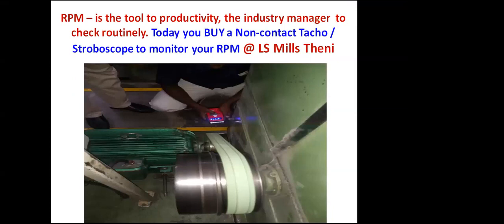RPM, as I was telling you before, is a routine activity in the given industry. Every industry thinks, I'll buy a 2,000 rupee or 3,000 rupee non-contact type tachometer. But the stroboscope is an excellent tool. Without switching off the motor or the machine, you can measure directly based on the optical pulses from the LED source. This is routinely done in many large-scale industries we have seen during our energy audits, especially the DCs, the designated consumers, mills or industries. They measure all their productive machines to know how much production RPM is getting lost each month or on each machine. They are able to study it and rectify the fault immediately. This is what is wanted in our industry.